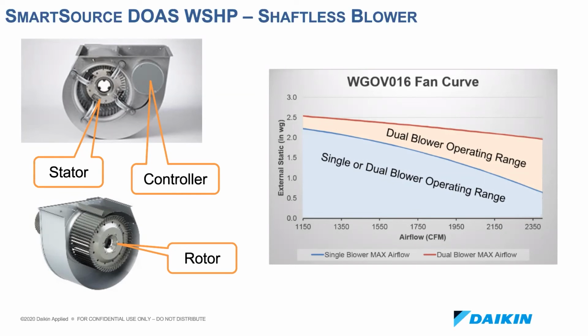Each unit has a wide range of airflow and external static pressure capability. All the units are capable of achieving at least 2 inches of static at nominal airflow. This chart shows the fan operating range for our nominal 1600 CFM model. With this unit, if using the single blower option, you can meet a requirement of 1200 CFM at 2 inches of static or 2000 CFM at 1 inch of static.